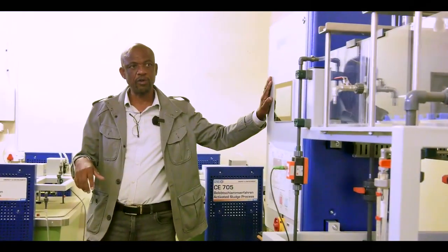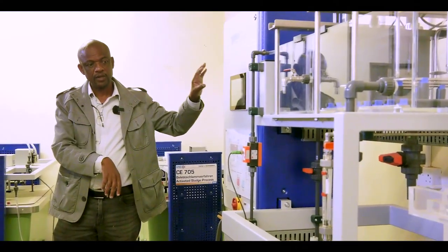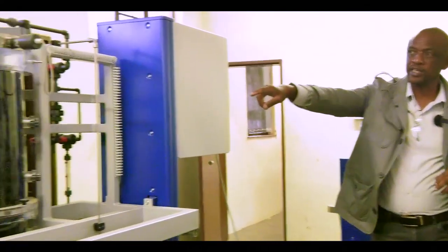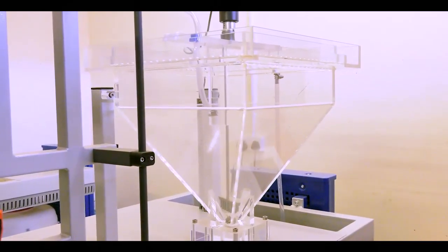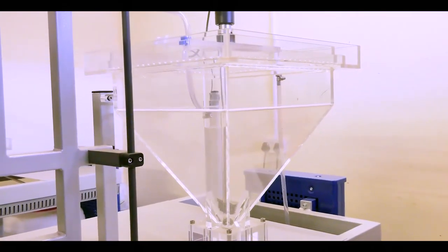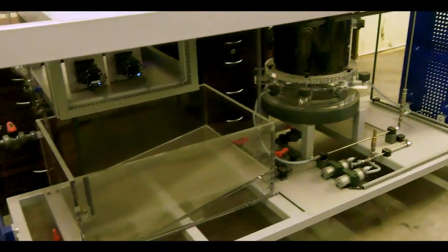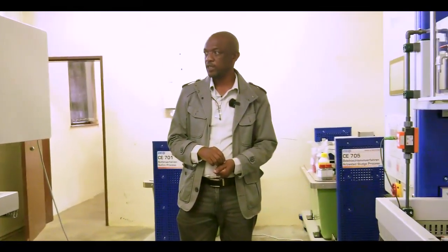On the systems themselves, we have control panels where they control the system in terms of temperature, in terms of dissolved oxygen, and all the other variables that we may want to analyze or assess. We also have, at the bottom end there, settling tanks where you separate whatever is being synthesized as water goes through the treatment. Then we have storage tanks at the bottom there where you can collect samples to analyze what could have improved the water as it comes from the supply line.